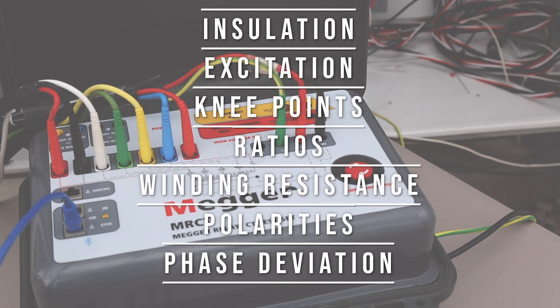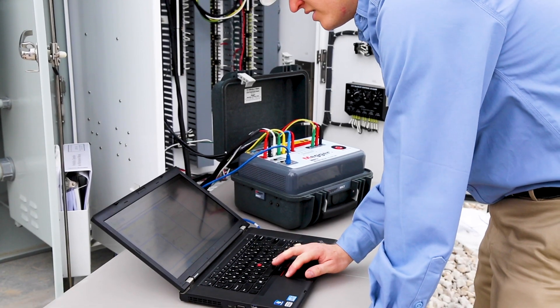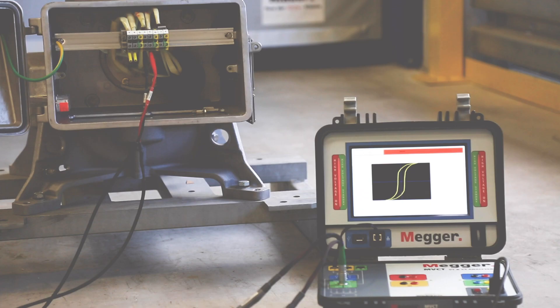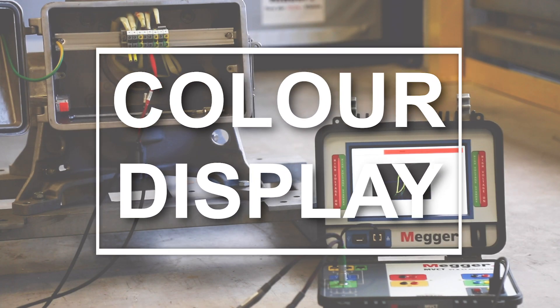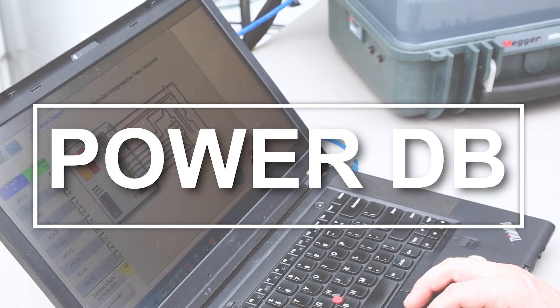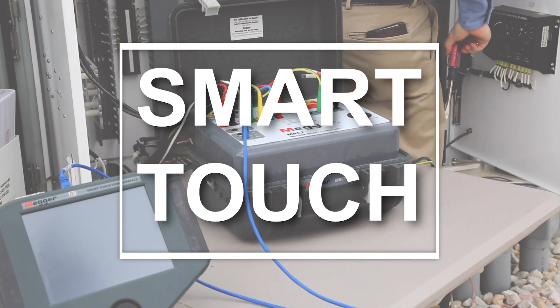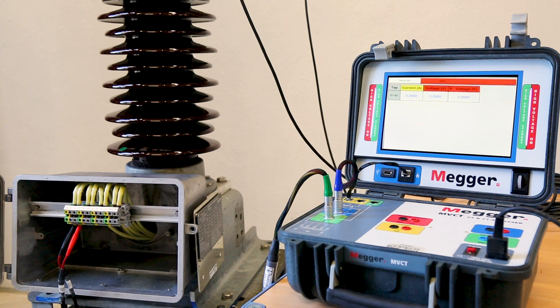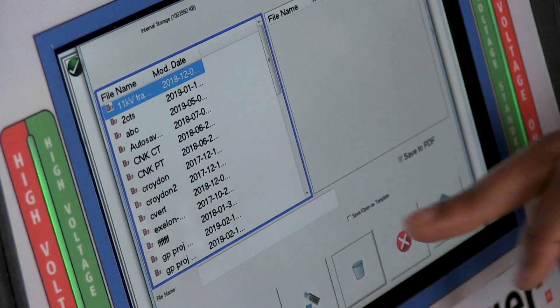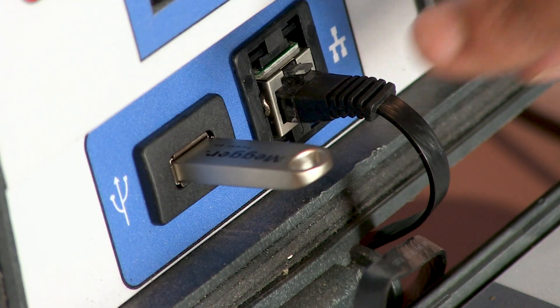When all tests are completed, both units will leave the CT in a demagnetized state. Both the MRCT and MVCT can be ordered and controlled with an integrated color display. Each unit can also be configured without an outer display and controlled using PowerDB software on a laptop, or from the SmartTouch View Interface, or STVI. When testing is complete, all results will be compiled into a one or two page report, which can be converted to PDF and saved to USB.